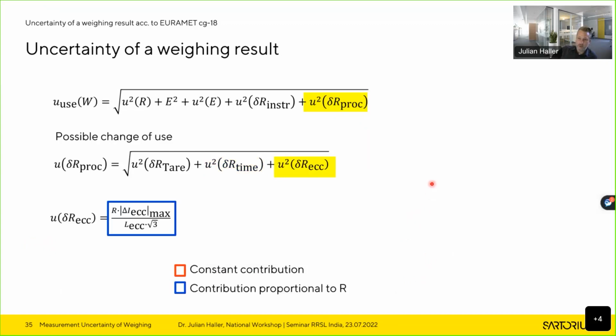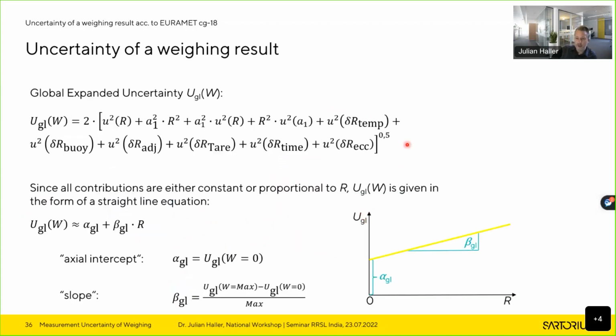And one further contribution that is taken into account is again that the user might load the balance more eccentrically than it has been done during the calibration. And this is again approximated by a respective contribution like that. And if we take all that together, we get a so-called global expanded uncertainty.